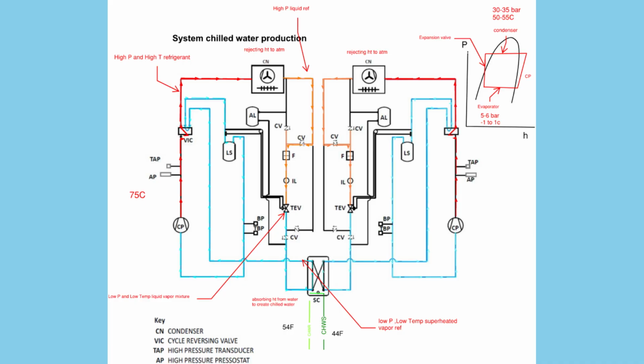3. Filtration and cleaning. The liquid refrigerant passes through a filter dryer and sight glass. The filter dryer removes moisture, dirt, and contaminants. The sight glass allows visual inspection for bubbles or impurities, ensuring the refrigerant is fully liquid before expansion. 4. Expansion. Next, refrigerant enters the expansion valve, TXV, or electronic. Here, it undergoes throttling, where its pressure and temperature drop significantly. The refrigerant leaves as a low-pressure, low-temperature liquid vapor mixture.